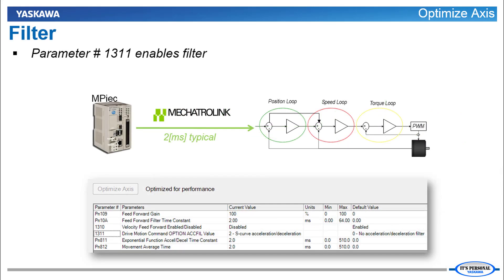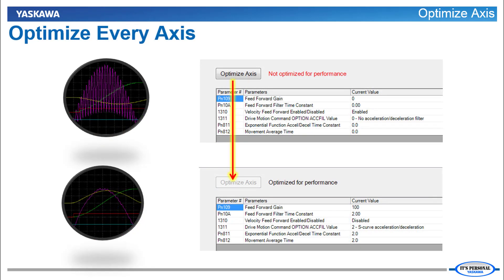Even without controller feedforward, the controller position command is still received at the Mechatrolink cycle. A servo motor tuned for high performance can respond very quickly, producing torque ripple at this rate. The command can be smoothed out using a filter selected by parameter 1311. This distributes the position command over the Mechatrolink cycle. The servo pack internal position loop receives the filtered position command, resulting in smooth motion with low torque ripple and reduced motor heating.